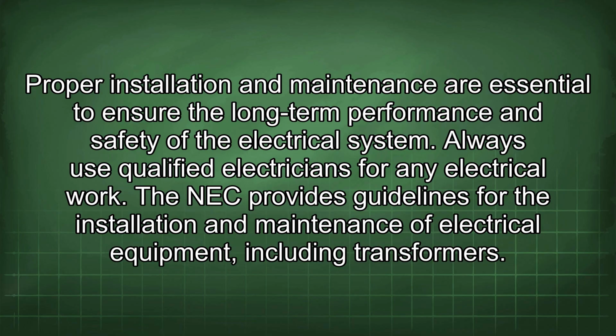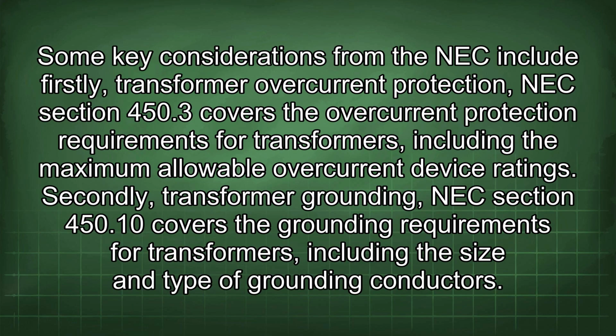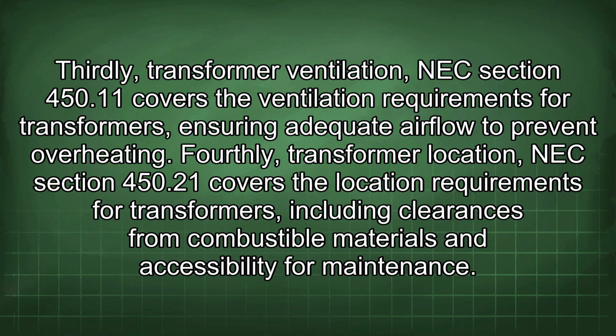The NEC provides guidelines for the installation and maintenance of electrical equipment, including transformers. Some key considerations from the NEC include: firstly, transformer overcurrent protection. NEC section 450.3 covers the overcurrent protection requirements for transformers, including the maximum allowable overcurrent device ratings. Secondly, transformer grounding. NEC section 450.10 covers the grounding requirements for transformers, including the size and type of grounding conductors. Thirdly, transformer ventilation. NEC section 450.11 covers the ventilation requirements for transformers, ensuring adequate airflow to prevent overheating.